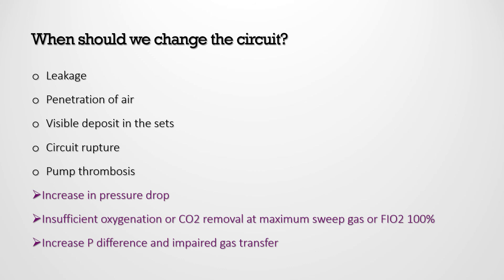Indications for circuit change include: leakage in the circuit, air penetration, visible deposits in the circuit tubing, circuit rupture, or pump thrombosis. When there is a problem with the oxygenator — such as increasing pressure drop, insufficient oxygenation or CO2 removal at maximum sweep gas or FiO2 100%, increased pressure differential, or impaired gas exchange — these reflect an oxygenator problem. Sometimes only the oxygenator is changed; in some cases, such as with certain CardioHelp systems, the whole circuit must be changed.